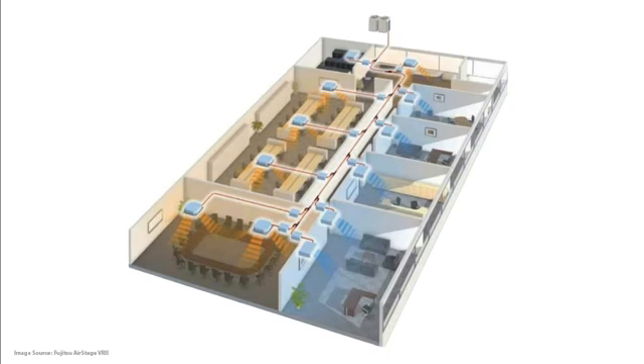Now when installing these, you need to pay attention to the zoning that you're setting up, because if you've got two cassettes in one area and they're classed as different zones, then there is potential that they're going to fight each other. So one is going to be calling for cooling, and the other cassette next to it is going to be calling for heating. So each of these will be fighting to service the load of the room. But we'll look at some of these technical details in later videos in this series on VRF units.